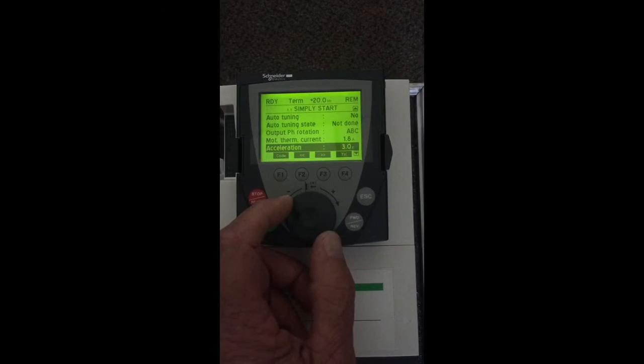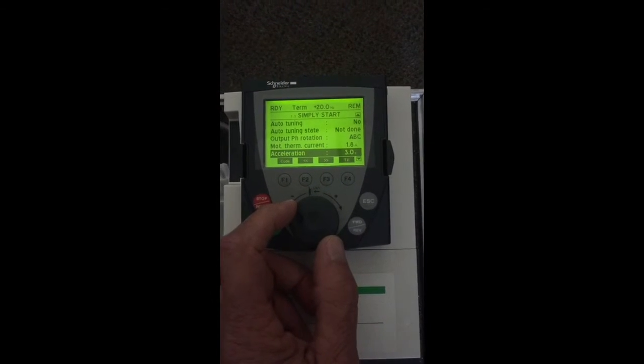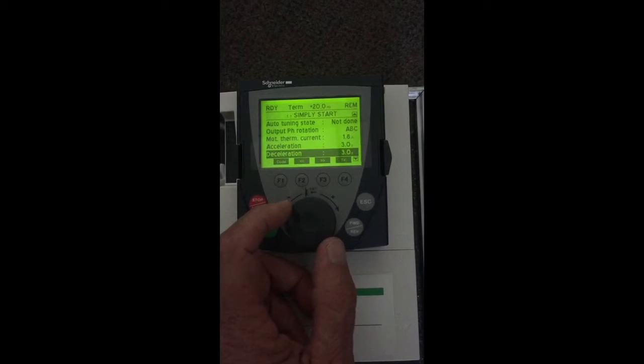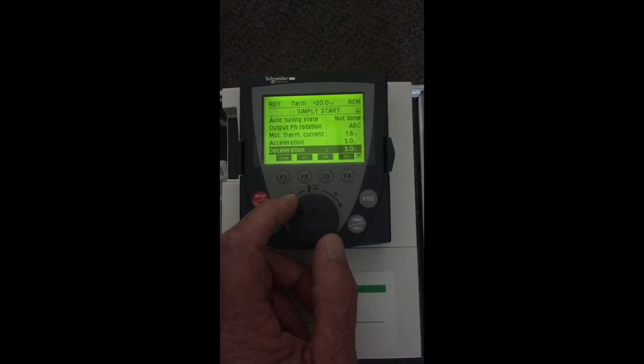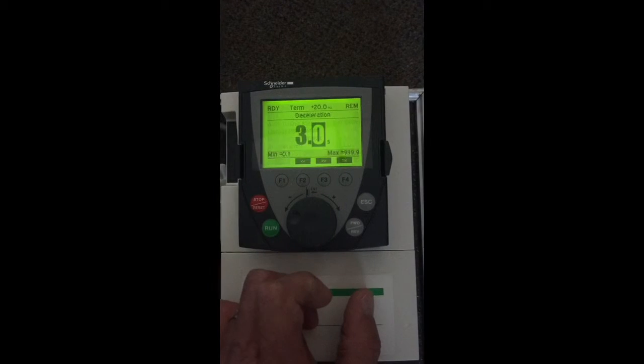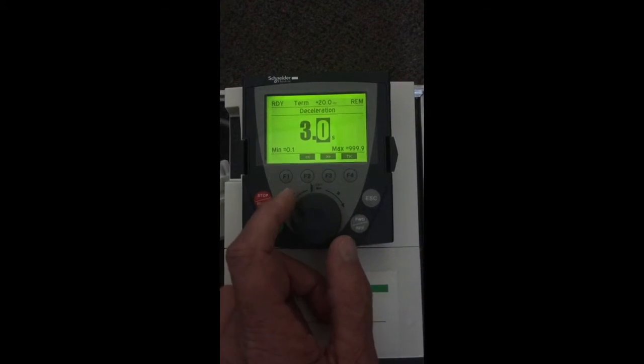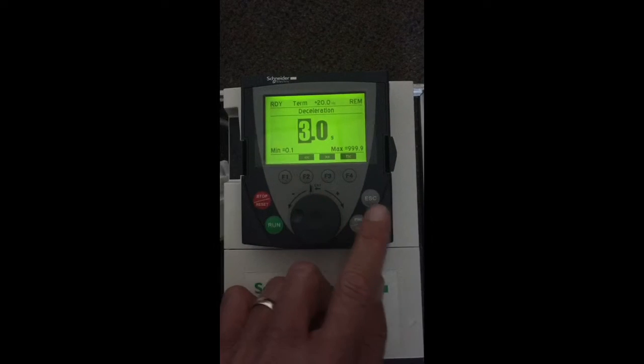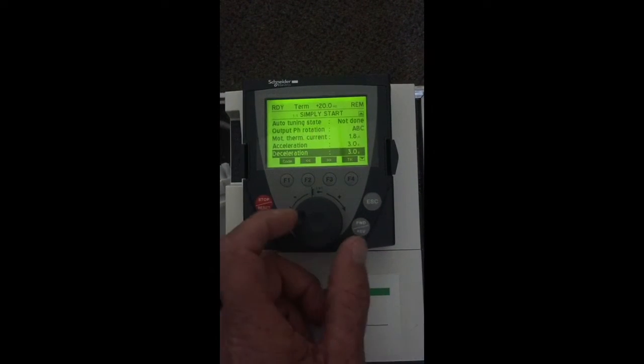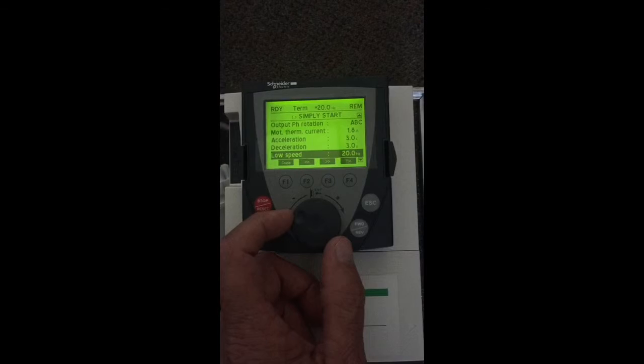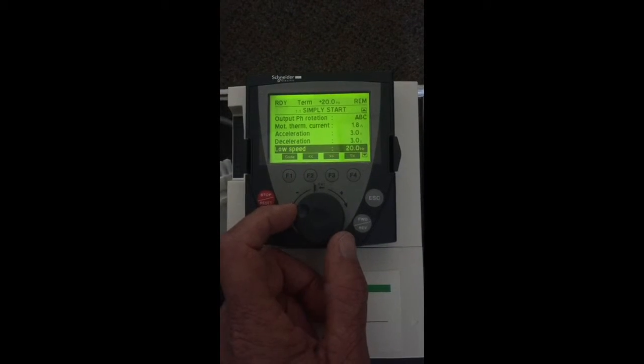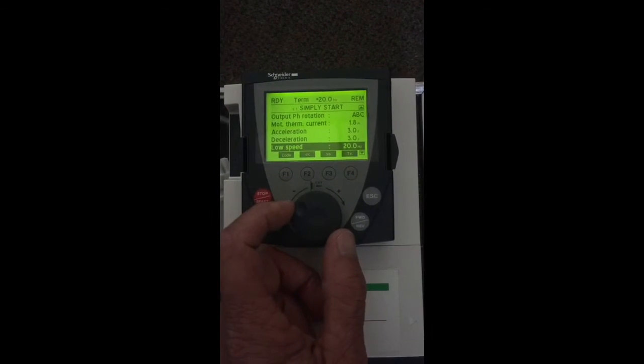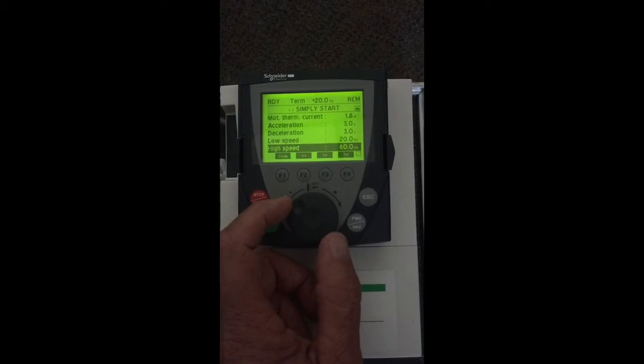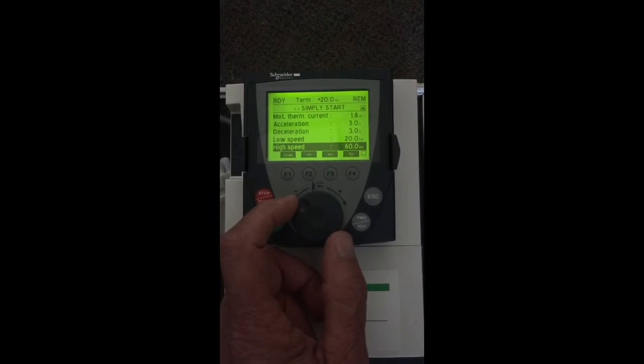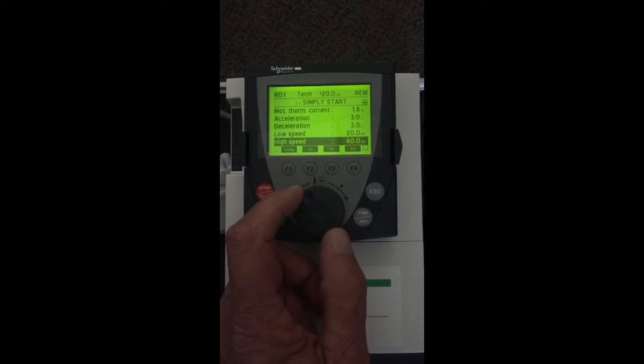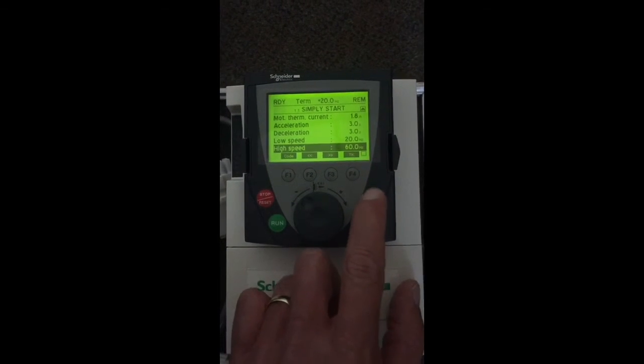Acceleration time. This is adjustable, how quick you want the motor to ramp up. Deceleration, same. To enter into the parameter, simply press the button, adjust your time that you want it to ramp up. Low speed that the motor will drop to during the minimal need. High speed will be your high end of your motor. These are in Hertz. Once you have all your parameters, you'll escape back out.